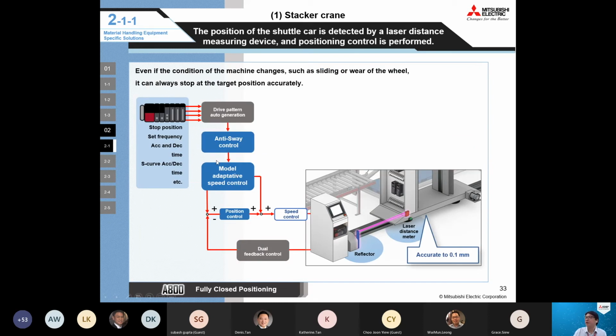Even if the position of the shuttle car is detected by a laser distance measuring device, position control is being performed. We have a laser distance meter to measure the distance and feedback from our encoder. We have dual speed control feedback, so that this helps enable it to always stop at the targeted position accurately, up to an accuracy of 0.1 mm.